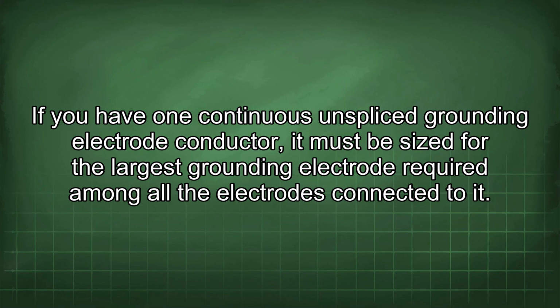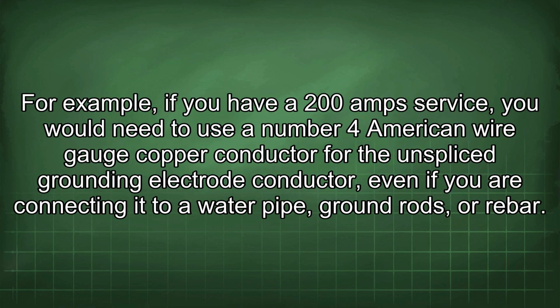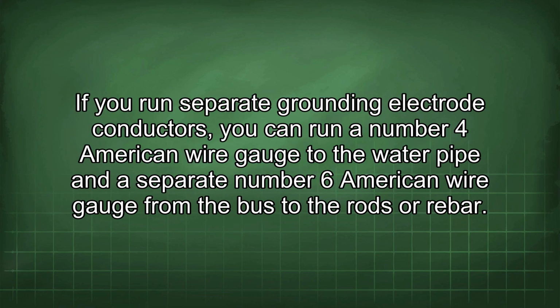If you have one continuous unspliced grounding electrode conductor, it must be sized for the largest grounding electrode required among all the electrodes connected to it. For example, if you have a 200 amp service, you would need to use a number 4 American wire gauge copper conductor for the unspliced grounding electrode conductor, even if you are connecting it to a water pipe, ground rods, or rebar. If you run separate grounding electrode conductors, you can run a number 4 American wire gauge to the water pipe and a separate number 6 American wire gauge from the bus to the rods or rebar.